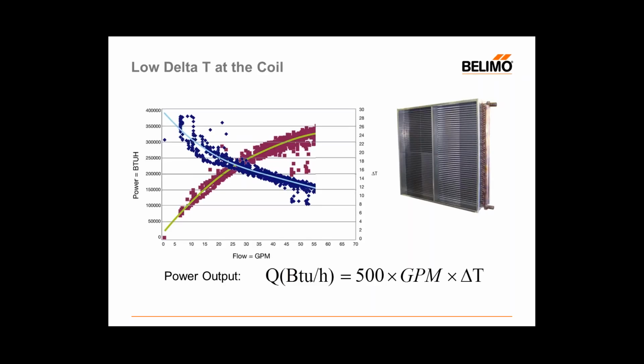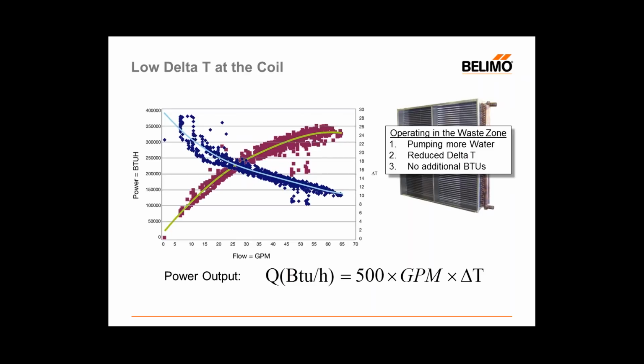What's most interesting to look at is what would happen if we put even more water through this coil. What we're looking at right here is actually a fairly good heat exchange profile. But if we continue to flood more water into this coil, three things happen, and all of them are kind of bad for us. So let's go ahead and take a look at what happens. The first thing that happens, obviously, is that we're pumping more water, so we're going to increase our cost of pumping. The second thing that happens is that we continue to decrease our delta T performance, and the third thing that happens is that we stop producing additional BTUs in the space.